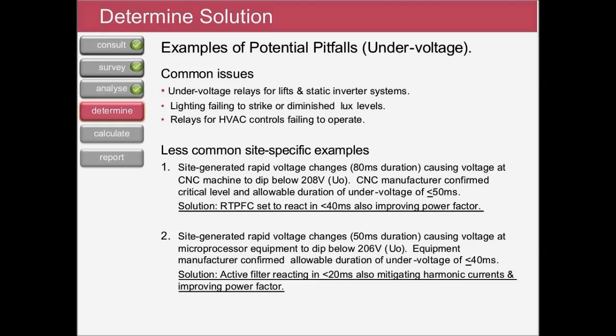Another similar example, we saw voltage dips around 206 volts, and they were causing microprocessor equipment to fail. The duration of these frequent events was generally between 50 and 150 milliseconds. However, the equipment manufacturer confirmed that the maximum tolerance here was only around 40 milliseconds. The solution in this instance was an active harmonic filter capable of reacting in less than 20 milliseconds. This solution had the added benefit of being able to mitigate harmonic currents on the network and improve the power factor. Now, the benefit of power quality solutions is sometimes difficult to quantify, but should not be overlooked.